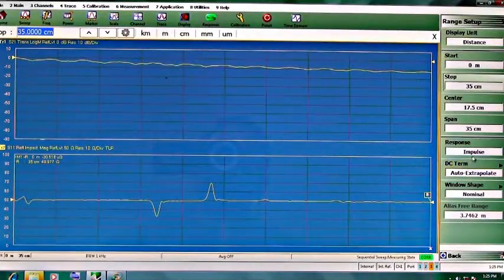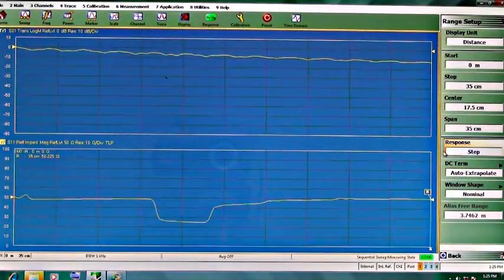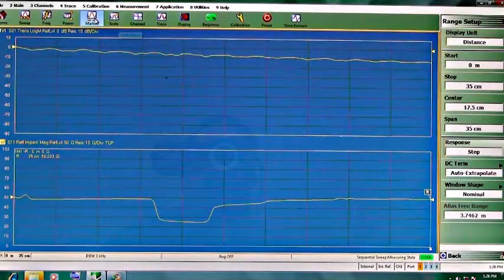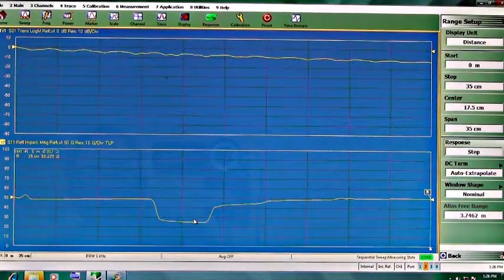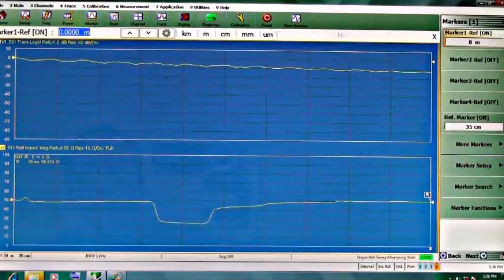So we want to actually look at this in step mode so we can identify it as a TDR type response, or give us actual impedance values and be able to tell easily whether it's inductive or capacitive. So now we're looking at the Beatty standard. This is the Beatty standard in air. And I can then put markers on there and take a look at the marker values, for example, and see if they are close. So the 50 ohm line is here. Two lines down, you can see 25 ohms is going to be between these two, and that's exactly where we are.